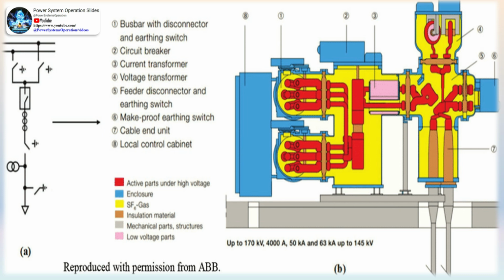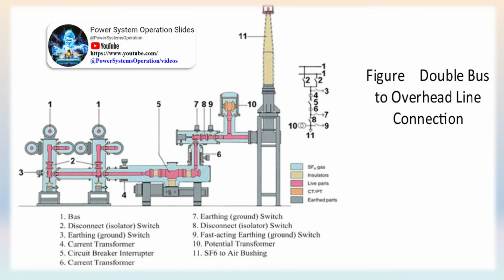Environmentally protected system. GIS technology is a good choice to use in Arctic or desert locations, as it can be enclosed in a building which is environmentally protected from extreme conditions. In addition to protecting the system components from extreme heat and cold, GIS technology encloses the electrical components within a Faraday cage, which shields the system from potential lightning strikes.